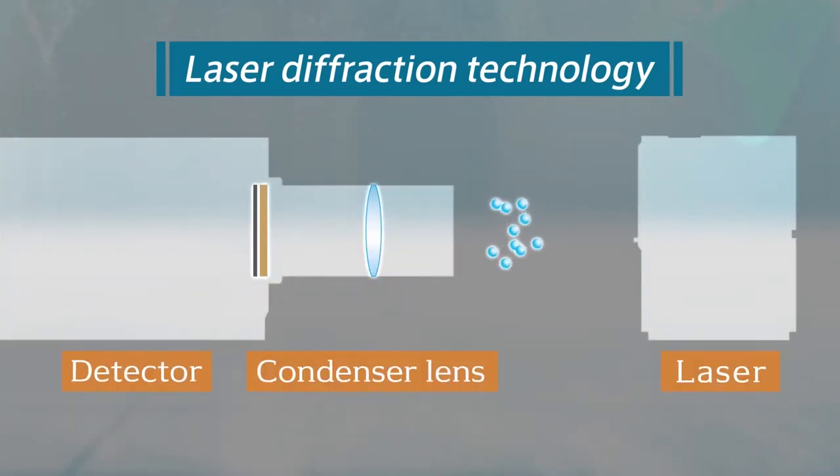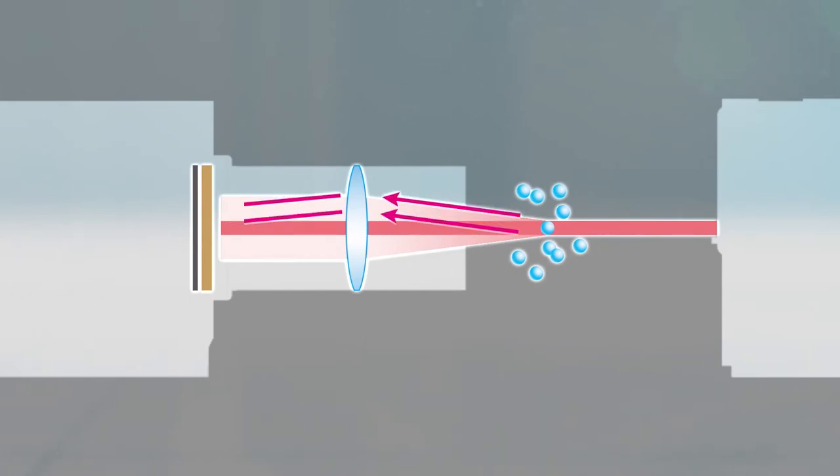Aerotrack 2 deploys laser diffraction technology for measurement. When droplets are irradiated with a laser, the laser light is scattered.